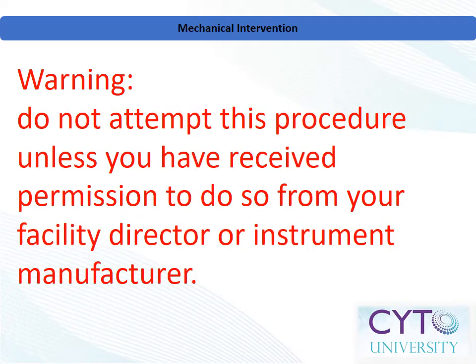The most disruptive solution for elimination of a clog is to disassemble the sample injection port and mechanically remove the clog. Clog removal can be achieved using sonication of the sample injection port apparatus, using a syringe filled with cleaning solution, or using a steel stylet. Warning: do not attempt this procedure unless you have received permission to do so from your facility director or instrument manufacturer. Always wear appropriate personal protective equipment prior to interacting with sample fluidics.